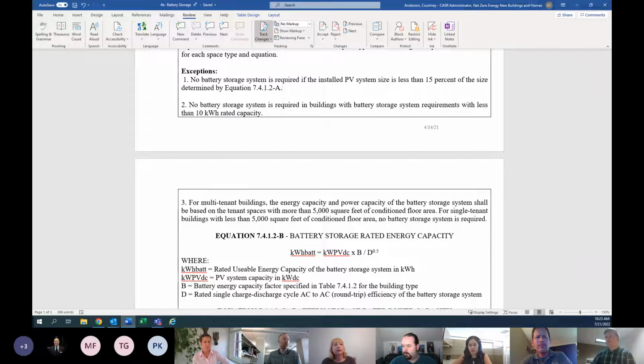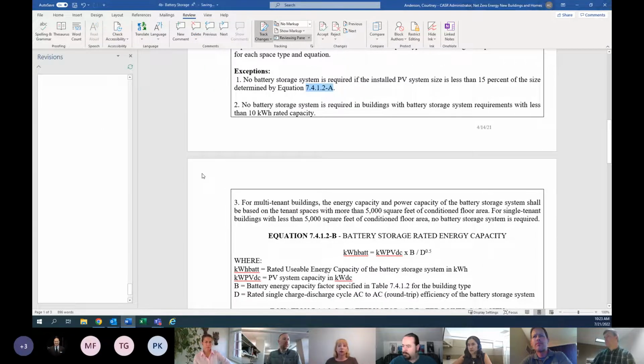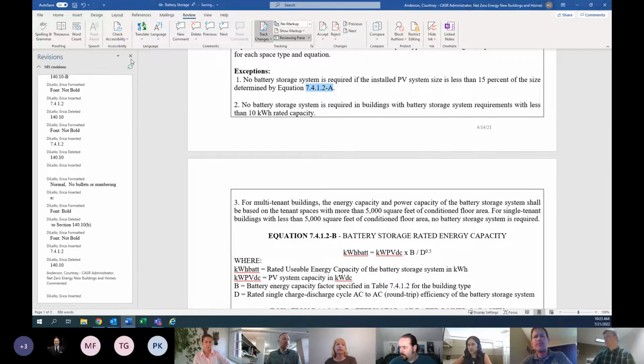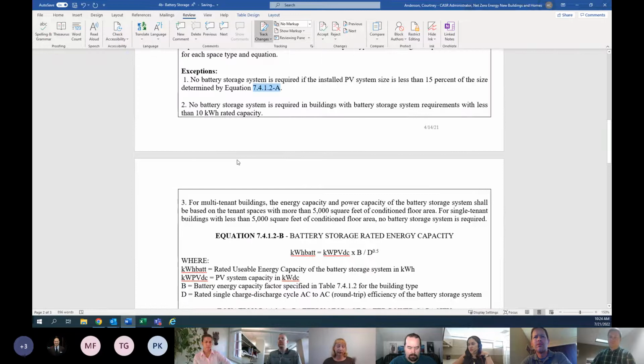The wording seems a little odd to me, but also not just that. In number 1, if I have just slightly over the 5,000, let's say my 6,000 square feet of conditioned space, you have to have a very large system in order to have the requirement for the battery storage system. So if I have a 6,000 square foot restaurant, then I can have a 900 kW system, which is very large, and still not require the energy storage system. So it goes to intent as well.